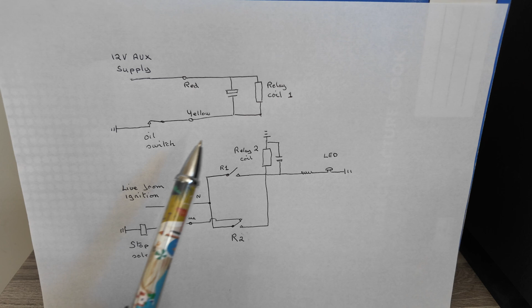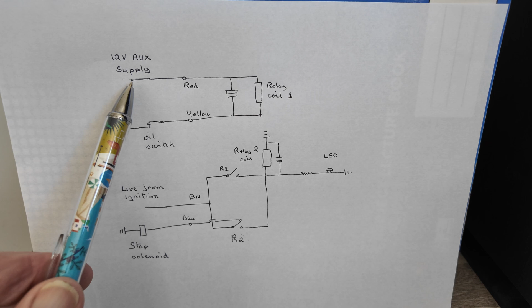The relay coil 1 up here doesn't do anything at all because the 12 volt auxiliary supply isn't there until the generator is running. So once the generator starts, get oil pressure, the oil switch opens and the 12 volt auxiliary supply appears on this rail on the red, but that does nothing because that switch is broken.